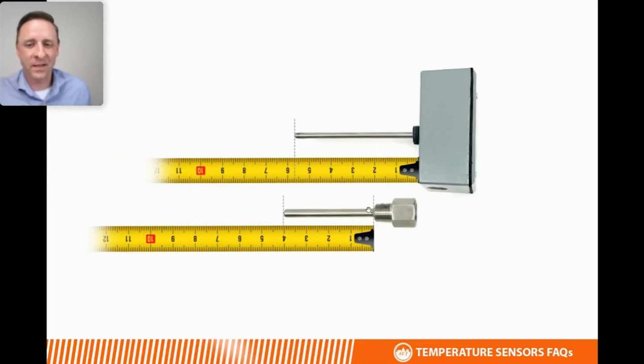So it goes back to how we label and measure immersion sensors. What we call a 4-inch immersion sensor is measured from the tip of the well to the base of the threads on the well. So a 4-inch sensor is going to be 4 inches from the base of those threads on the well to the tip of that well. This 4-inch sensor will actually use a probe that's a little bit longer due to the length of these threads.